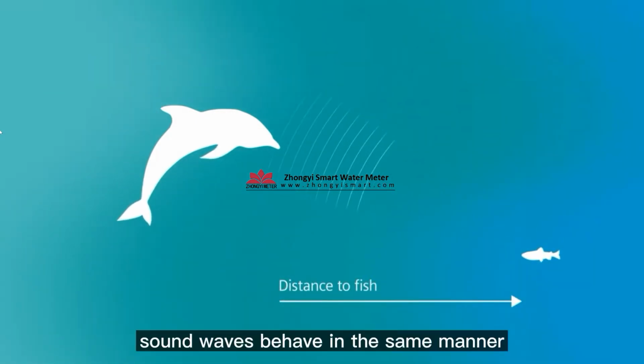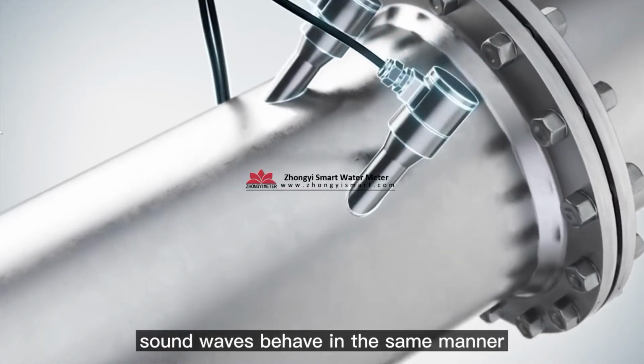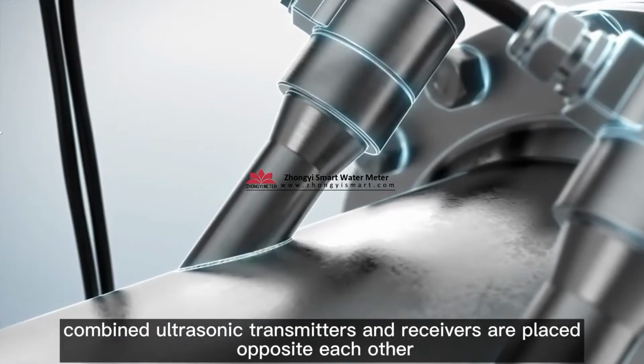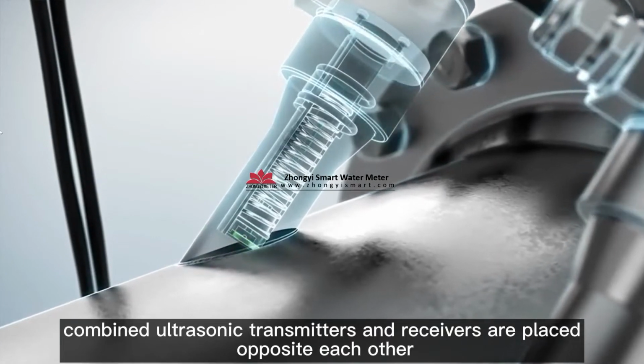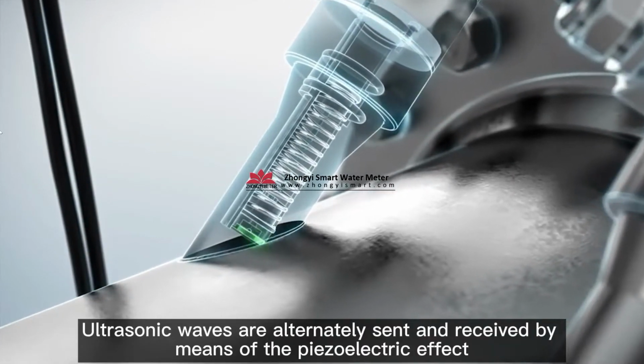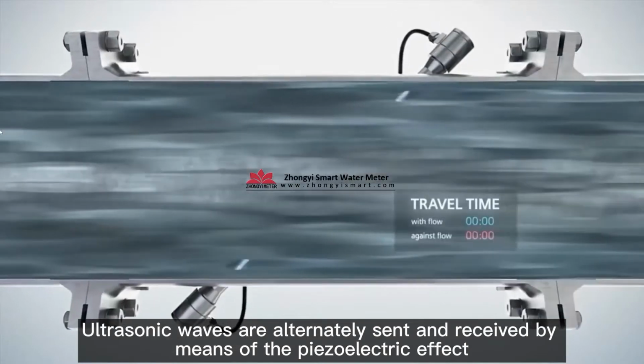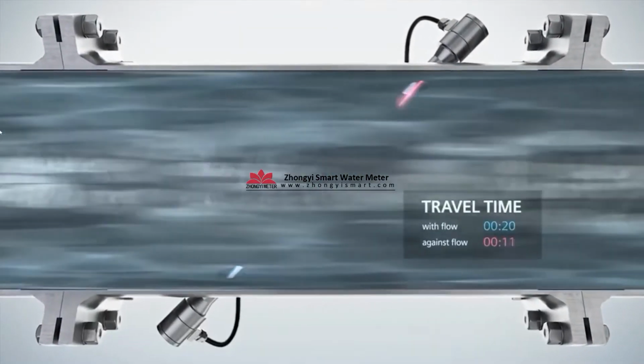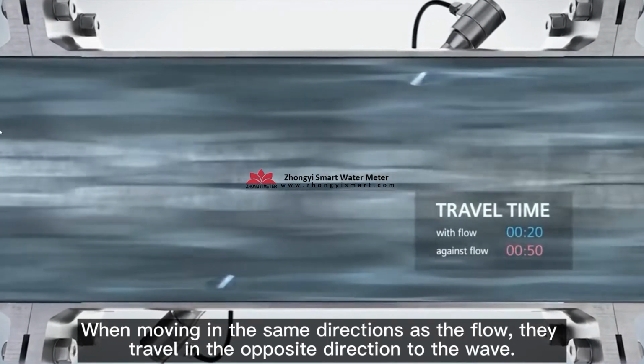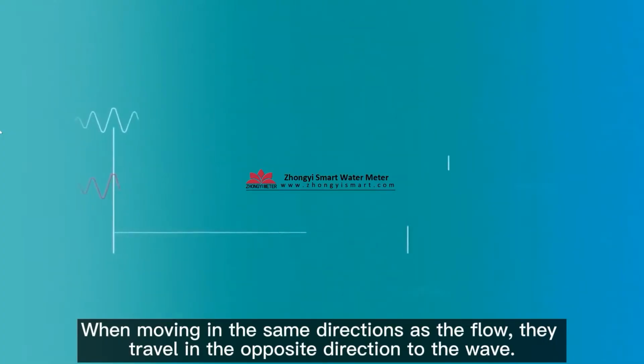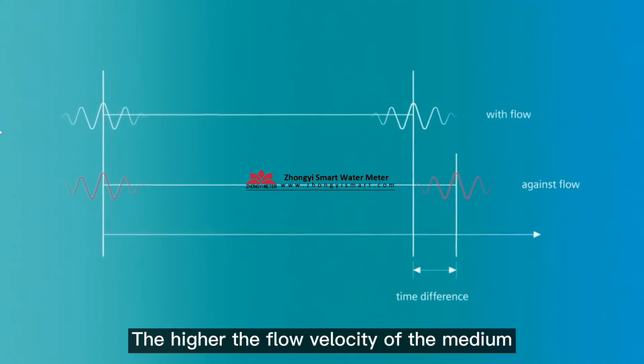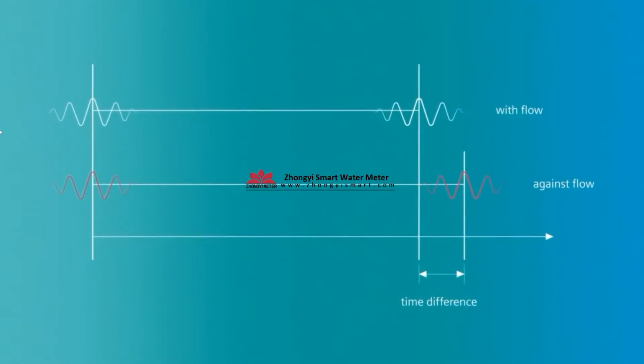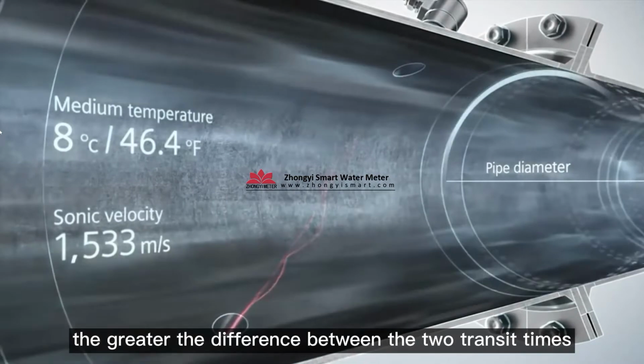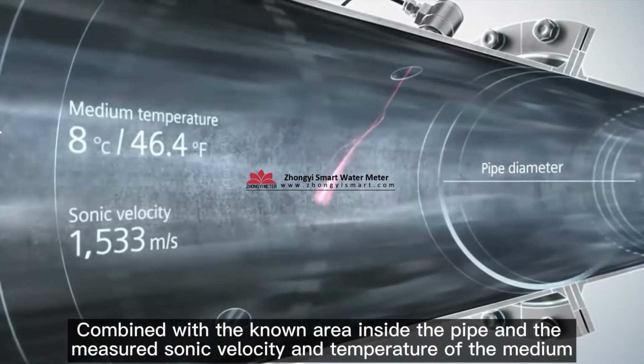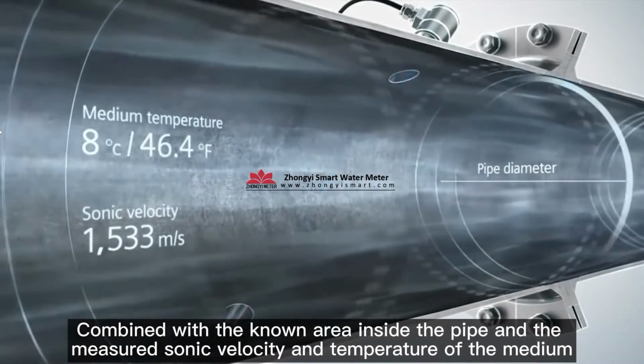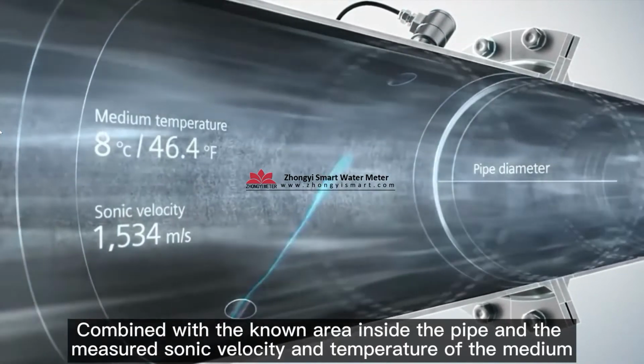In a flow system, sound waves behave in the same manner. Combined ultrasonic transmitters and receivers are placed opposite each other. Ultrasonic waves are alternately sent and received by means of the piezoelectric effect when moving in the same direction as the flow. They travel in the opposite direction to the wave. The higher the flow velocity of the medium, the greater the difference between the two transit times, combined with the known area inside the pipe and the measured sonic velocity and temperature of the medium.